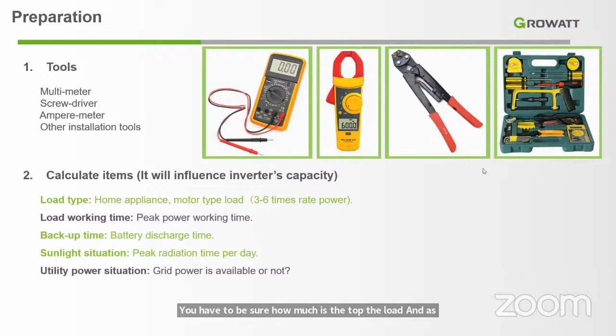A crimper is also usually recommended. I'd advise you to have this crimper instead of putting all the cables together in a not-so-tidy way. Otherwise you can get hot spots because the contact isn't good, so it's better to use a crimper too. That would be pretty much everything for tools. All of these steps must be addressed before the installation, before the buying -- you have to be sure how much the charge, the load is, and the voltage in the plant.